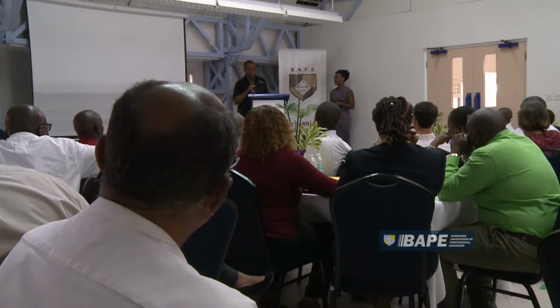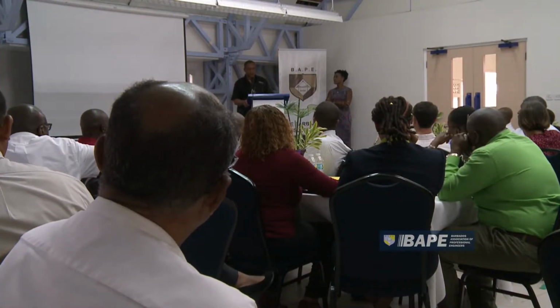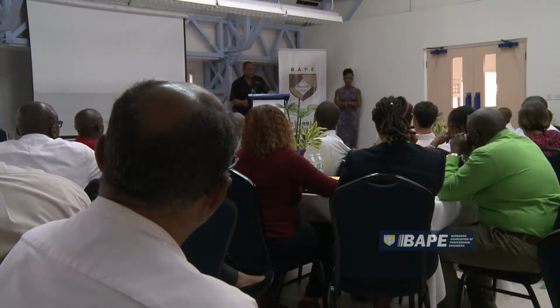Thank you, Paula. Part of our specifications is that the contractor is required to provide airside readings after they go in and balance. Now, as I said, I will design a system and put airflow values that I'm expecting in various areas. But when you actually install the system, you may get different readings, and you're going to try and balance to what I get. So within 10% is what is an acceptable difference, either more or less.